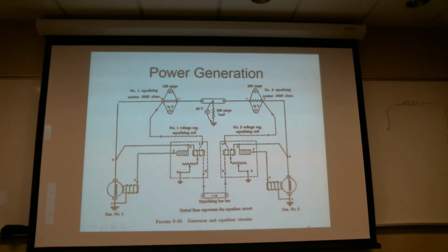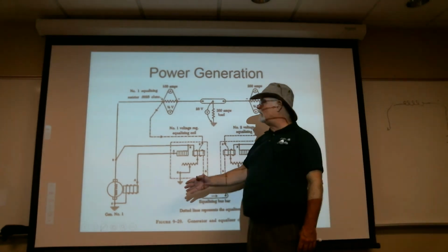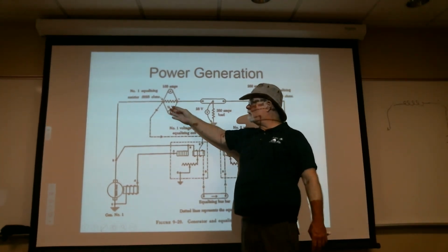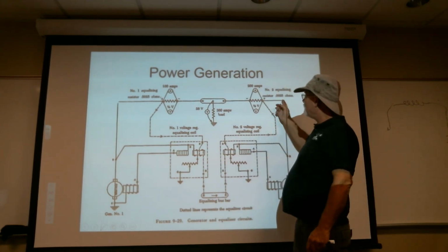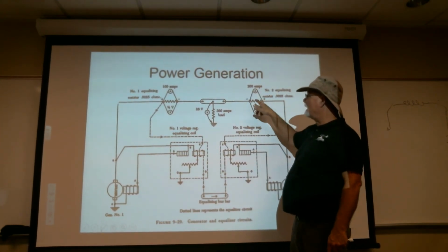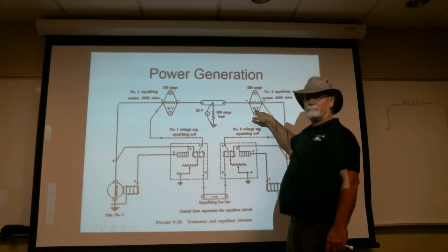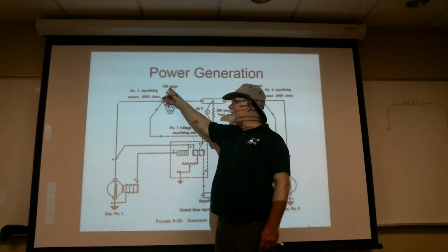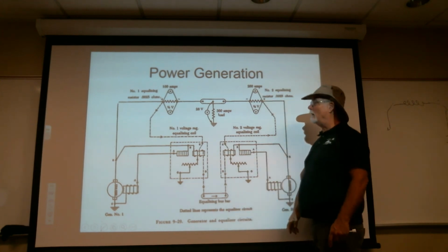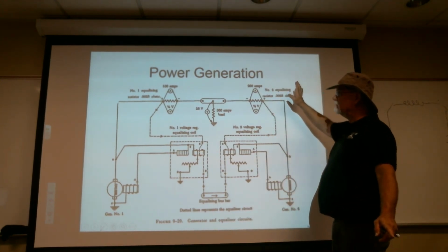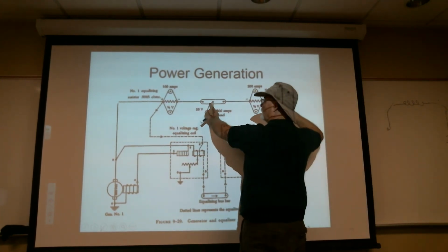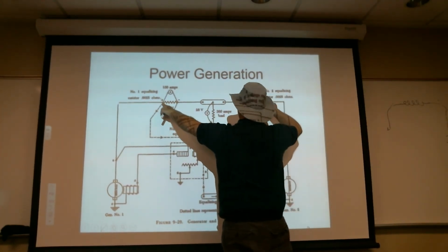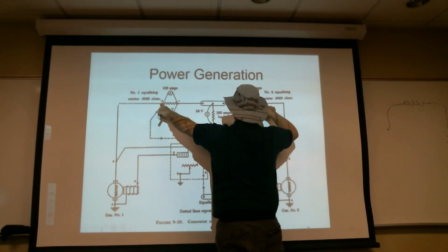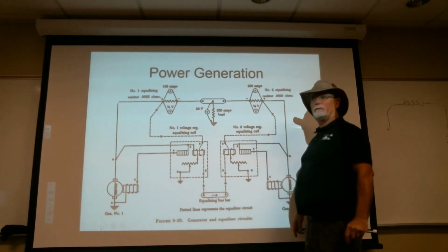But when one generator isn't putting out as much as the other, this one's not putting out as much. So what's going to happen is this guy at 200 amps is going to create a half a volt drop here, while this guy at 100 amps is only going to create a quarter volt drop. So that means that while this is 28 volts, this is actually 27 and 3/4, and that might be 28 and 1/4. So there's a little bit of a voltage difference between the two.